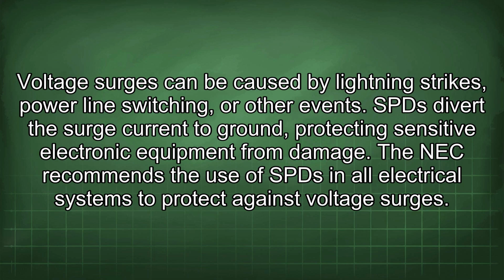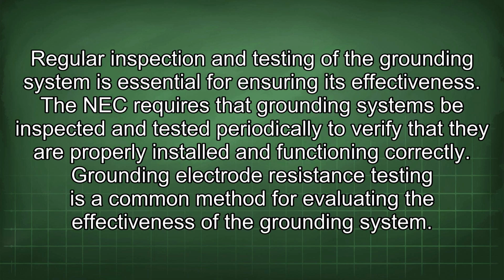SPDs divert the surge current to ground, protecting sensitive electronic equipment from damage. The NEC recommends the use of SPD in all electrical systems to protect against voltage surges. Regular inspection and testing of the grounding system is essential for ensuring its effectiveness.